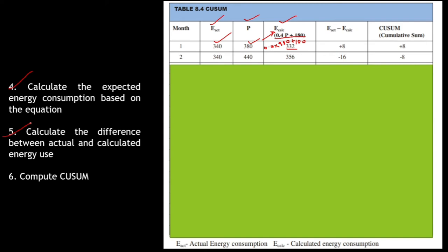Step 5: calculate the difference between actual and calculated energy use. You find E_actual minus E_calculated. For the first point, E_actual = 340 and E_calculated = 332, so the difference is +8. For the next point, E_actual = 340 and E_calculated = 356, giving 340 − 356 = −16. The difference can be positive or negative.